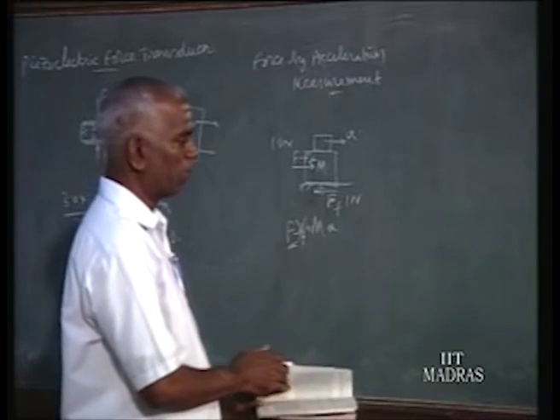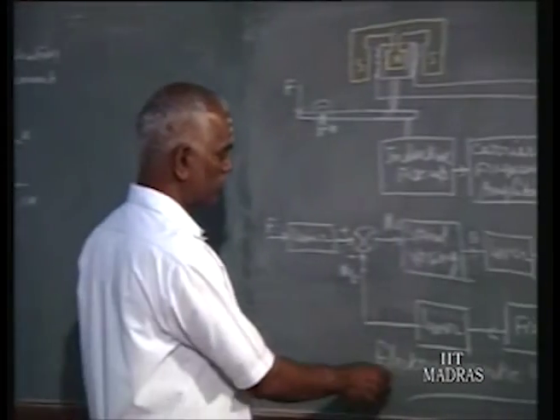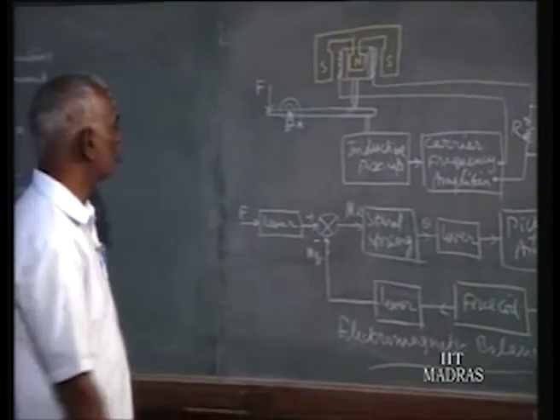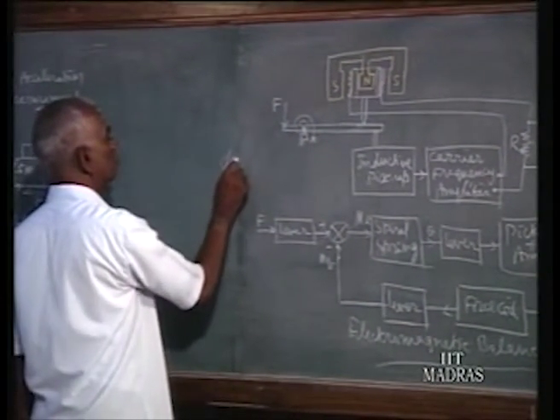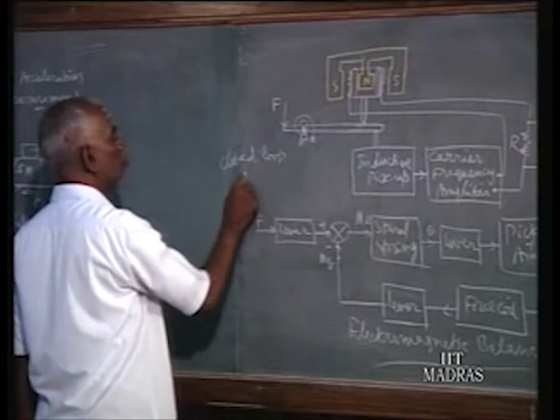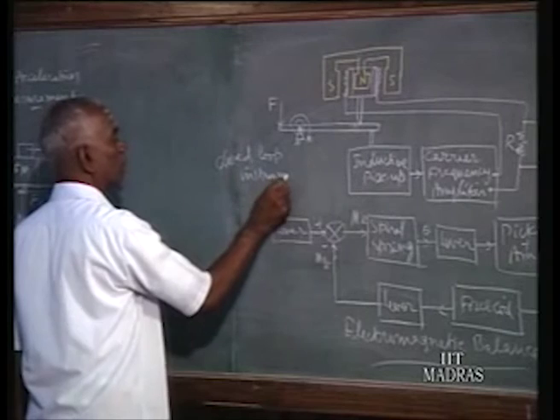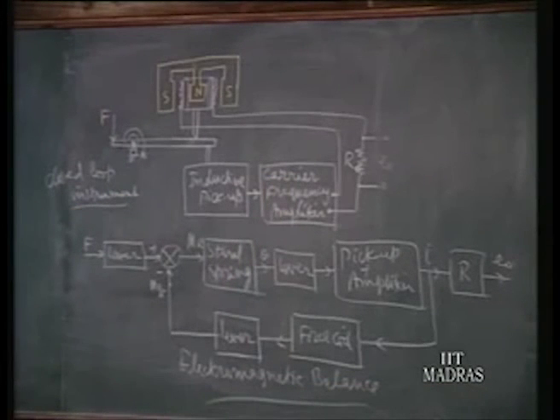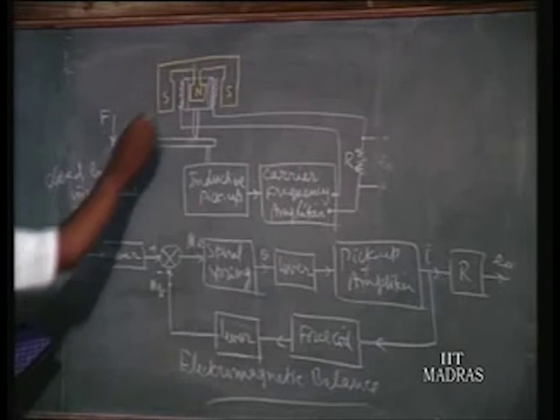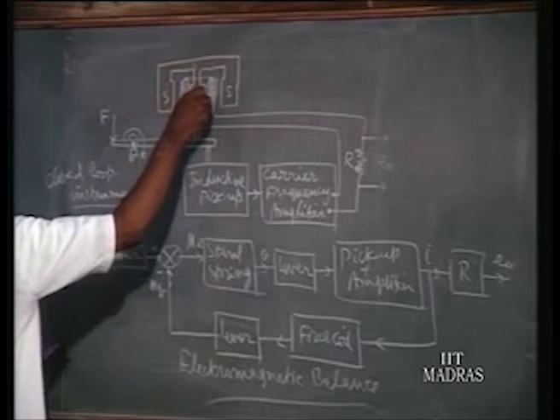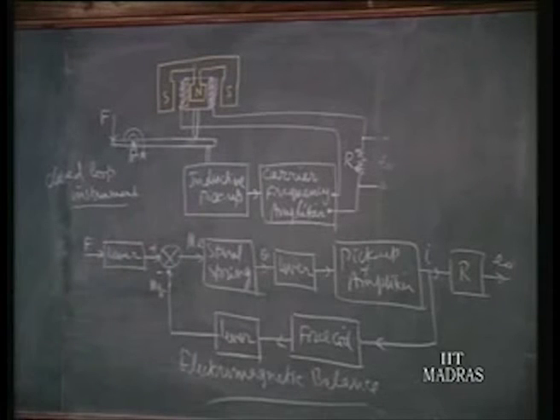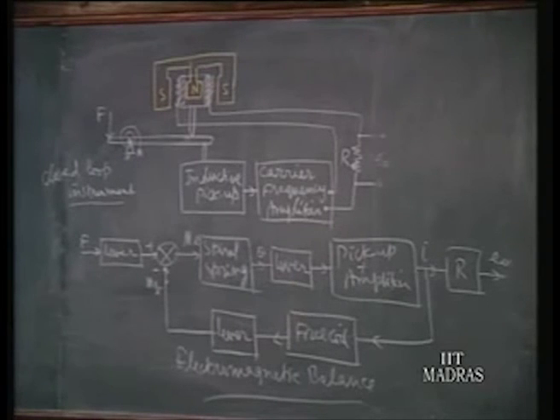It's called the electromagnetic balance. This is a closed loop instrument. So far, all the instrumentation, the earlier versions you have seen, are open loop instrumentation, but now it is a closed loop instrumentation. The general advantage of closed loop instruments is there for this instrument also. That means they have higher accuracy, say 0.1% accuracy you can get, whereas in open loop we can get only 1 or 2% accuracy.